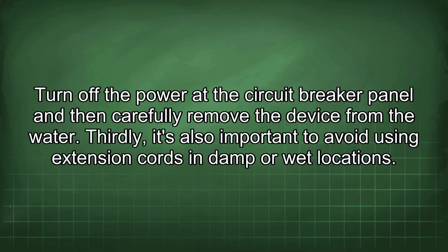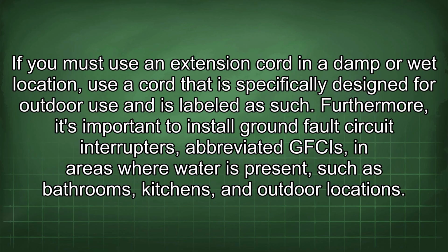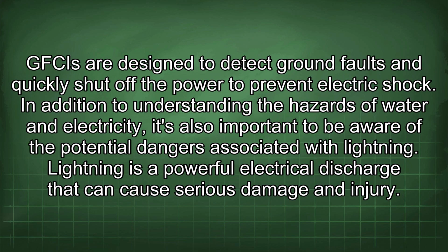Thirdly, it's also important to avoid using extension cords in damp or wet locations. If you must use an extension cord in a damp or wet location, use a cord that is specifically designed for outdoor use and is labeled as such. Furthermore, it's important to install ground fault circuit interrupters, abbreviated GFCIs, in areas where water is present, such as bathrooms, kitchens, and outdoor locations. GFCIs are designed to detect ground faults and quickly shut off the power to prevent electric shock.